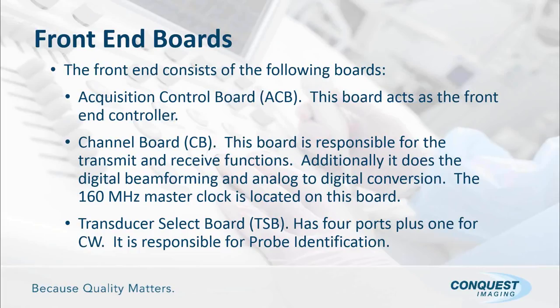You have your transducer select board, and again, this is what we call the probe interface board. That's where we plug probes in. On the Epiq 5 and 7, we have 4 ports for the standard probes and 1 port for CW, which is continuous wave. One of the primary functions of the transducer select board is probe identification. There are 3 places probe identification can get messed up. If you plug in a probe and it's not identifying, the first place you should look is whether the probe is capable of IDing itself. Perhaps a probe got dropped and it damaged the circuitry inside the probe. When that happens, you plug it in and it simply can't ID itself, so you don't get any ID on the screen.